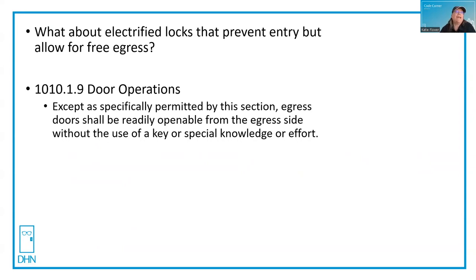For all other doors, Section 1010.1.9 for door operations is in effect: egress doors shall be readily openable from the egress side without the use of a key, special knowledge, or effort. If UL 294 isn't referenced here, then you don't need it for standard electrified hardware that allows free egress. You may be able to use this citation to talk to your AHJ and get them to see your side.